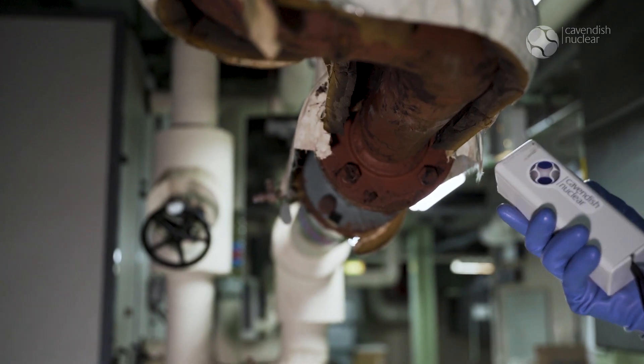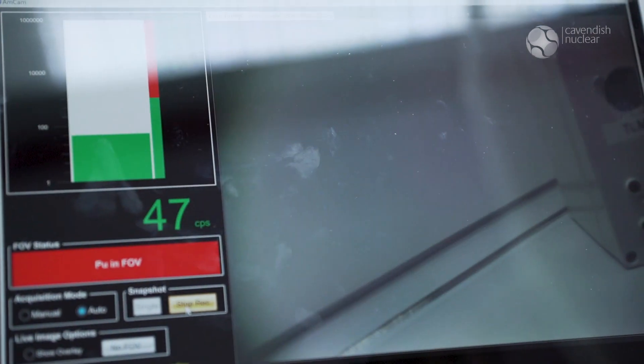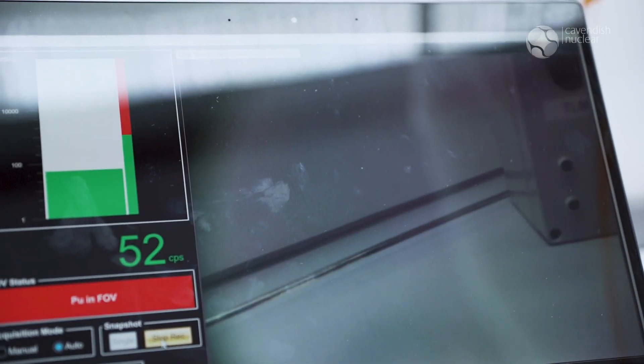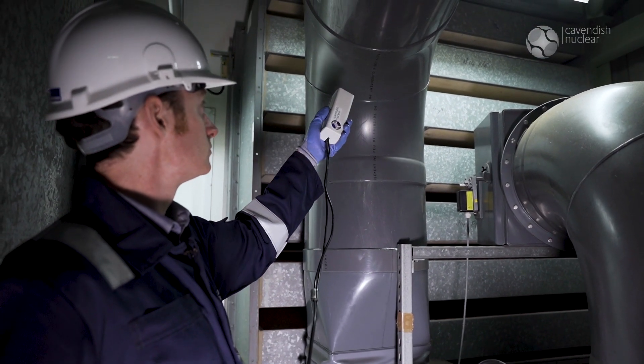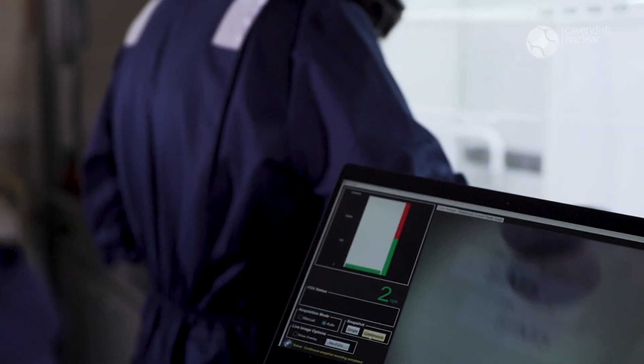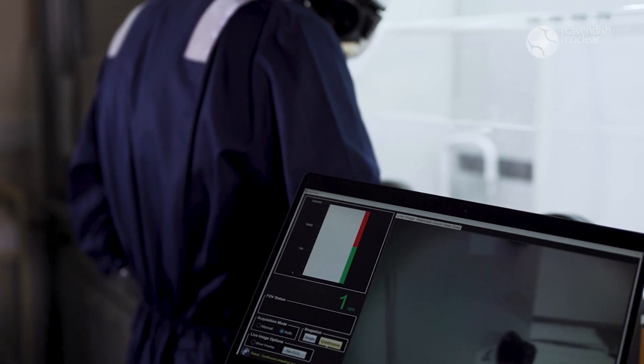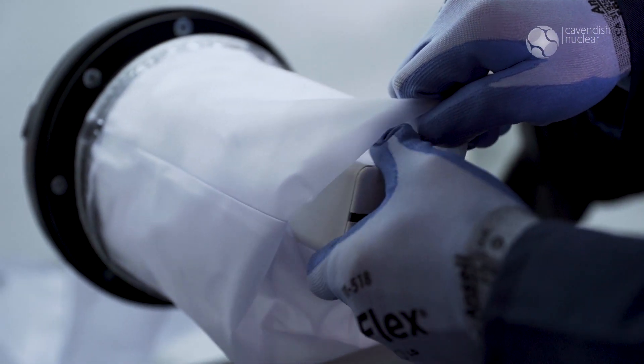Amcam is a lightweight handheld real-time inspection device that will identify areas of high alpha contamination and allow them to be targeted for cleanup. Amcam is very simple and intuitive to use and it can be operated by a single user, but perhaps works best as a two-person team, one person deploying the detector head and the other person holding the laptop and providing guidance to the user.